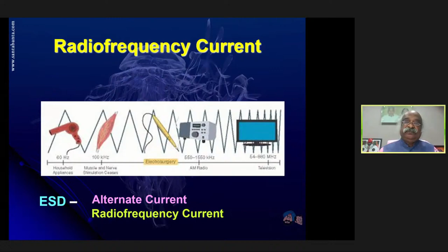Now, what is the difference between electrocautery versus electrosurgery? Electrocautery is the application of direct current to an instrument of high resistance, that is a wire, to produce heat. And this heated wire is applied directly to tissue to destroy it. And that's known as electrocautery.